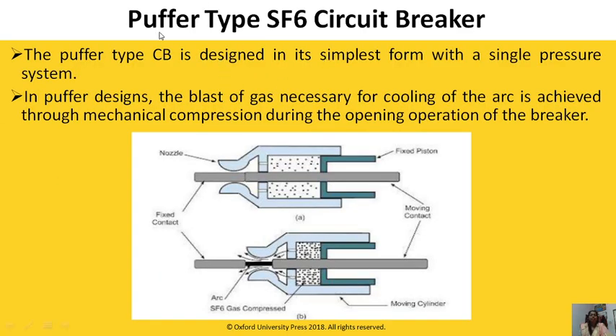The puffer type circuit breaker is designed in its simplest form with a single pressure system. In the puffer design, the blast of gas necessary for cooling of the arc is achieved through mechanical compression during the opening operation of the breaker. During the opening operation, only a closed chamber is present.